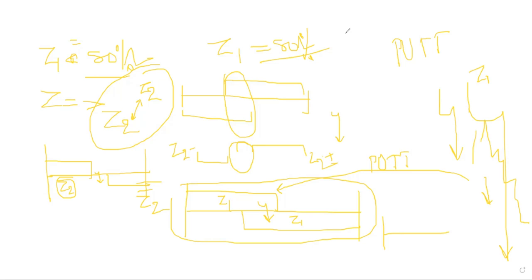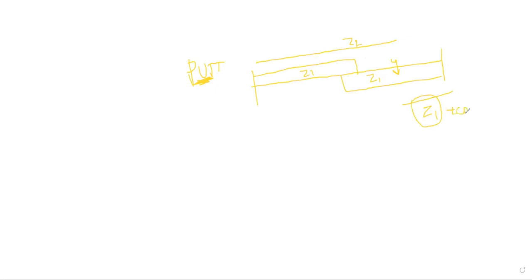I need this explanation with a drawing. Underreach, in the underreach permissive scheme, what is happening? This is zone 1 and this is zone 1. Suppose a fault occurred here. For this end it is zone 2, for this end it is zone 1. So it detects zone 1 and sends the carrier to this end. This end has already picked up at zone 2 and is receiving the carrier, so it will also operate. This is the permissive underreach scheme.